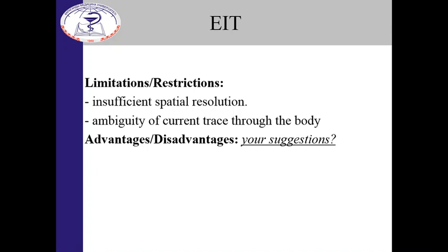Also, please realize that the image here is reconstructed according to electrical properties. That's why this image does not reflect our perception. The lung wouldn't be red or look as we can receive it by our eyes. It's really out of vision. It provides an image that doesn't fit our perception because it's an electrical, in quotes, image.